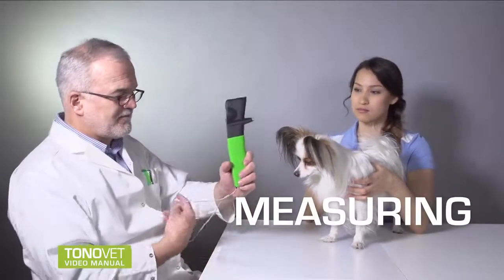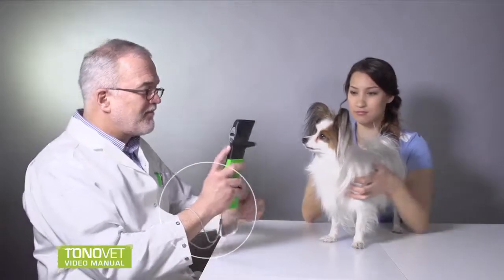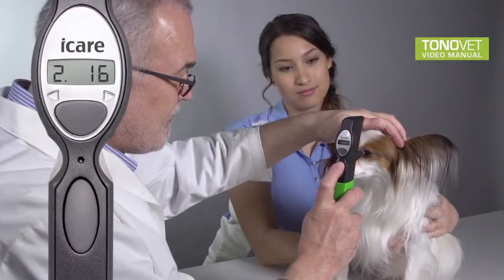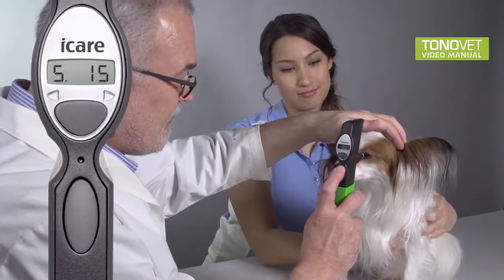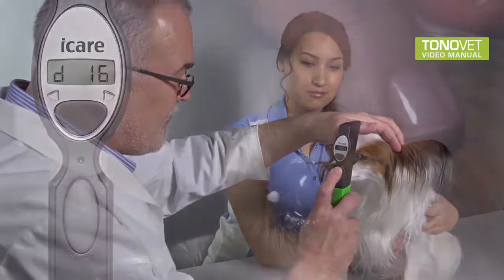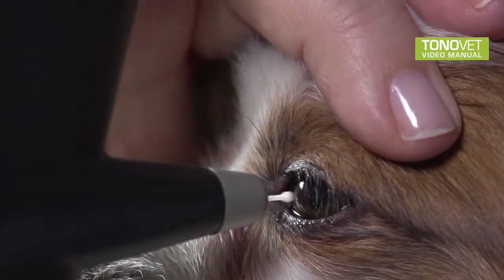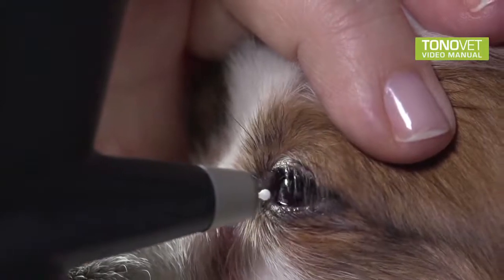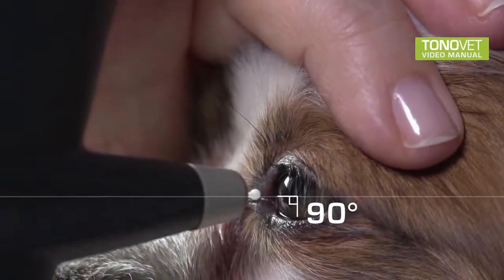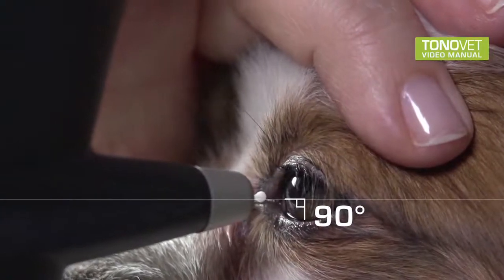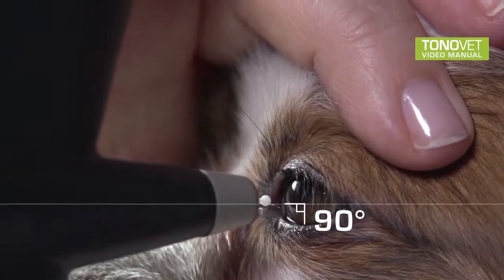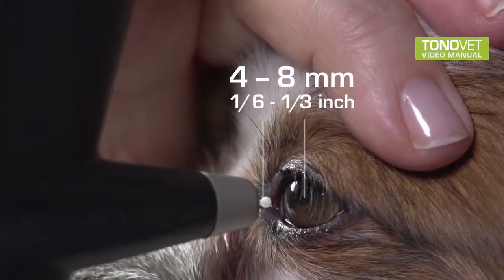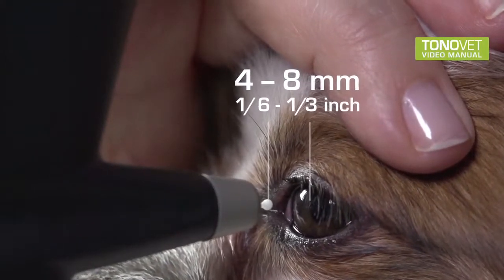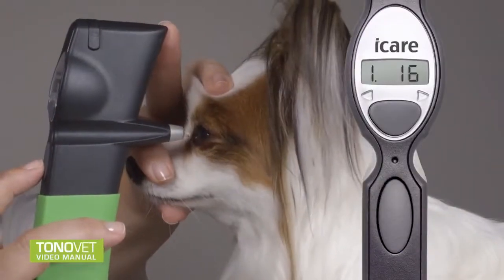Measuring. Always use the wrist strap to protect the tonometer from accidentally dropping. 6 measurements are needed to obtain the final reading, which is an average of the 4 mean single measurements. Bring the tonometer near to the patient's eye. Make sure the tonometer is in a horizontal position, perpendicular to the central cornea. The distance from the tip of the probe to the cornea should be 4 to 8 millimeters, or 1/6 to 1/3 inch, respectively. Press the measuring button 6 times.